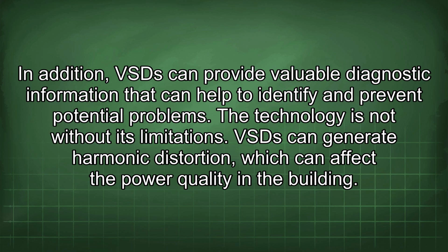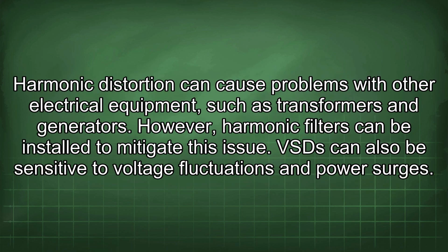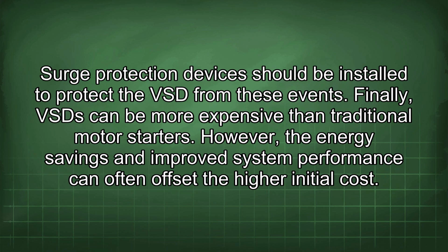The technology is not without its limitations. VSD can generate harmonic distortion, which can affect the power quality in the building. Harmonic distortion can cause problems with other electrical equipment, such as transformers and generators. However, harmonic filters can be installed to mitigate this issue. VSD can also be sensitive to voltage fluctuations and power surges. Surge protection devices should be installed to protect the VSD from these events.